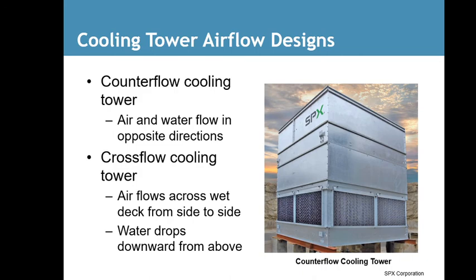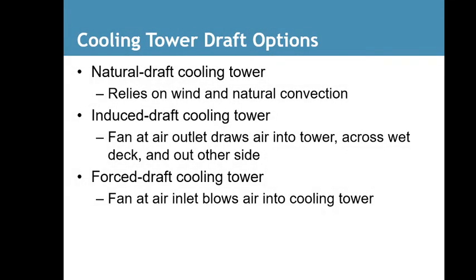Cooling tower draft options. Natural draft cooling tower relies on wind or natural convection. Induced draft cooling tower, fan at air outlet draw air into the tower across the wet deck and out the other side. And then there's a forced draft cooling tower. Fan at the air inlet blows air into the cooling tower. These are terms you'll need to know from this chapter.